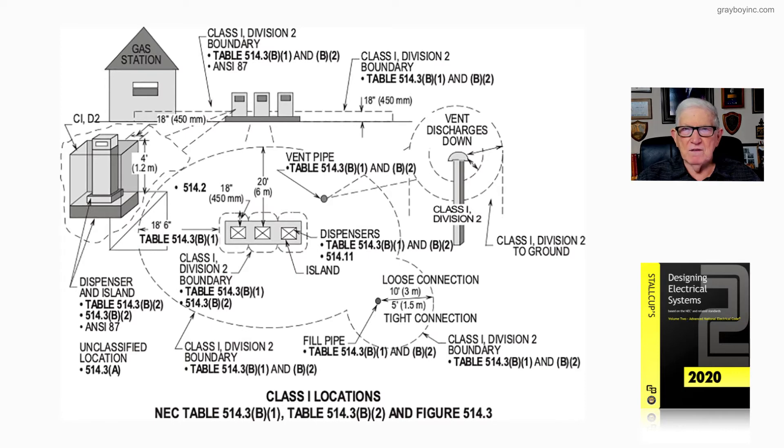But now looking at the island itself with the dispensers, notice that you're going to count out 18 inches, because that's a Class 1 Division 2, and then from there it's 18 feet 6 inches on out, giving you a total of 20 feet overall.